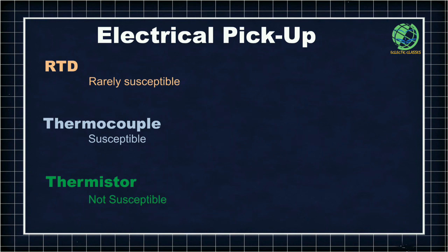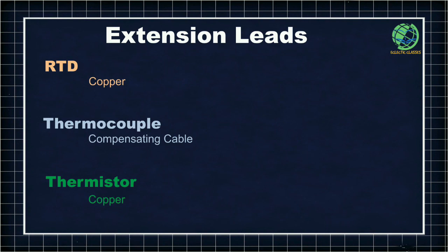When it comes to electrical pickup, RTDs are rarely susceptible to pickup of electrical noise from their surroundings. Thermocouples are susceptible to pickup of electrical noise, while thermistors are not at all susceptible to electrical pickup. In terms of extension leads, RTDs and thermistors use copper as extension leads, while thermocouples use compensating cable depending on the type of thermocouple used.